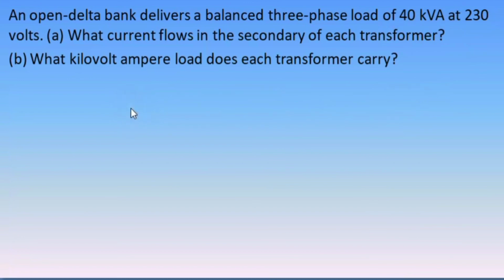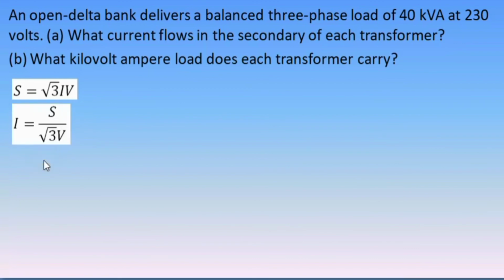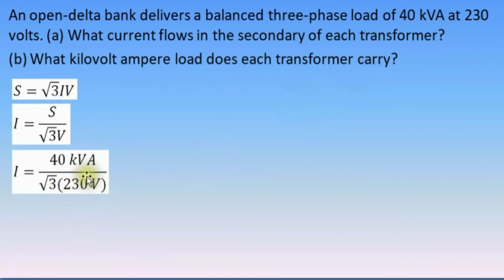To determine the current that flows in the secondary of each transformer, from the formula of the apparent power in a three-phase system, cross multiply square root of 3 and voltage to the other side of the equation, we have current equals apparent power divided by square root of 3, divided also by voltage. Substitute the values. We have 40 kVA divided by square root of 3 and 230 volts. The answer is 100.409 amperes.